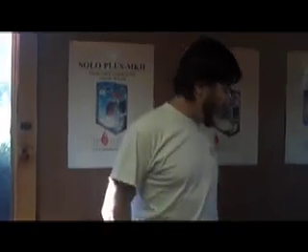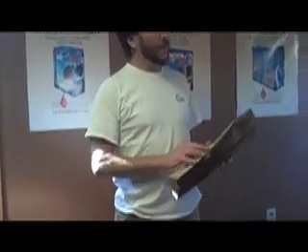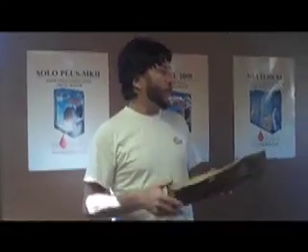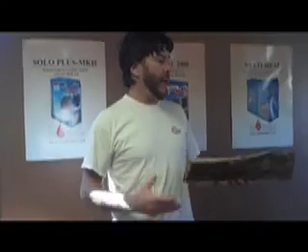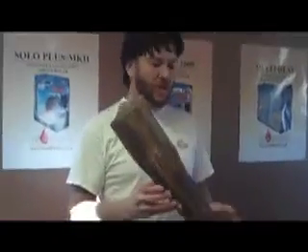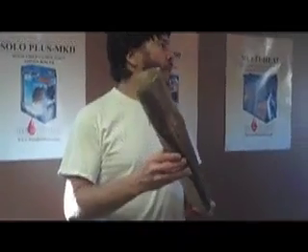This is the same size that we have at the Knoll Farm. This unit is super high-tech in that cord wood all has a different amount of water in it, and each one burns at a different rate — and as it's burning it changes. Versus pellets, which burn the same from beginning to end, so you don't really have to change the way it burns through the cycle. Most people put up with burning cord wood just at a straight rate — they throw it in a wood stove, set it, maybe adjust it once, and that's it. But the problem is you need to change it through the whole burn so that you get the most energy out, because it gives you the most energy if it's burned at a certain rate.